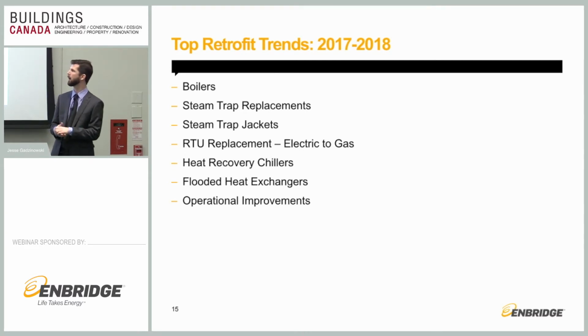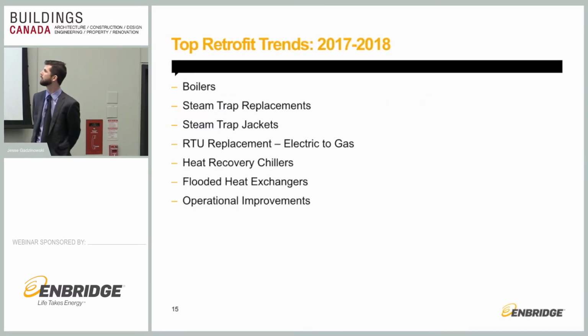Some companies out there are adding an extra compressor onto the chiller package, and then spinning that compressor and getting that low-grade heat up to high-grade, so that you can actually use the chiller to chill where it's needed, but then offsetting a large part of your heating load with the chiller. So it's an interesting upgrade. If you'd like any more information on that, please talk to me after, but it's a good opportunity.